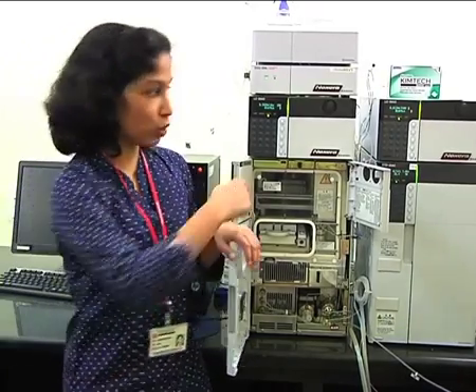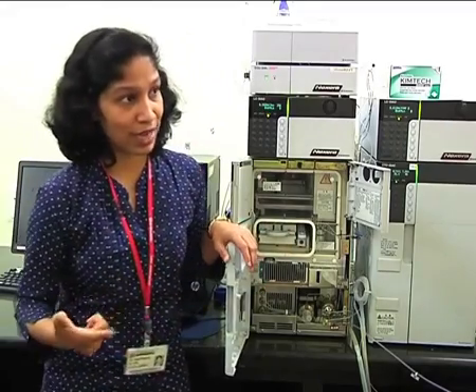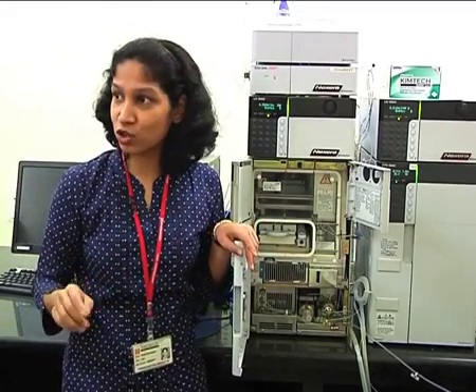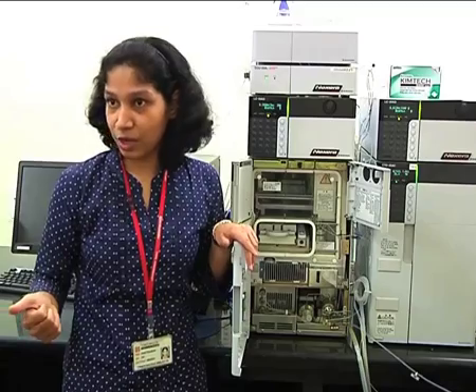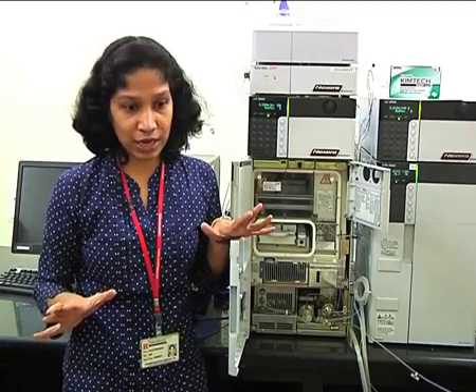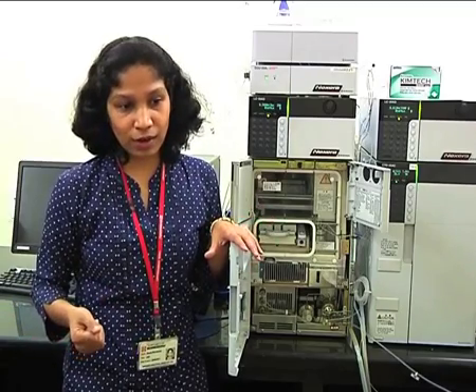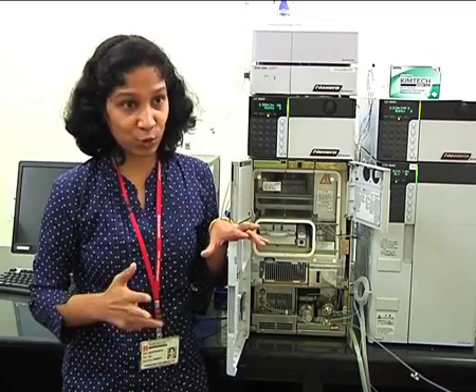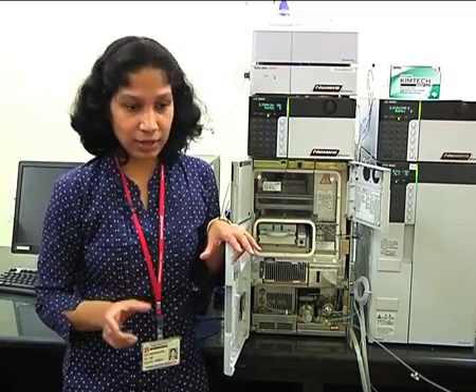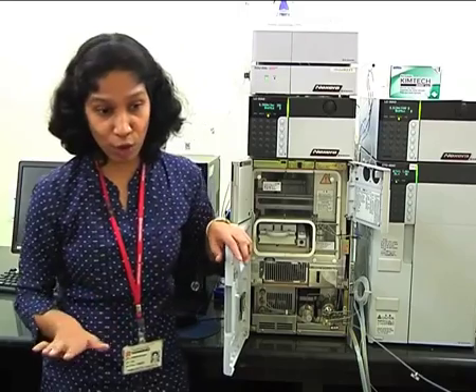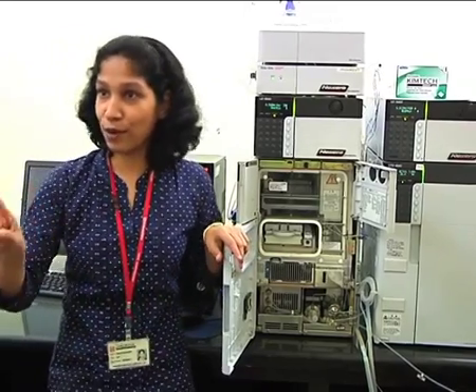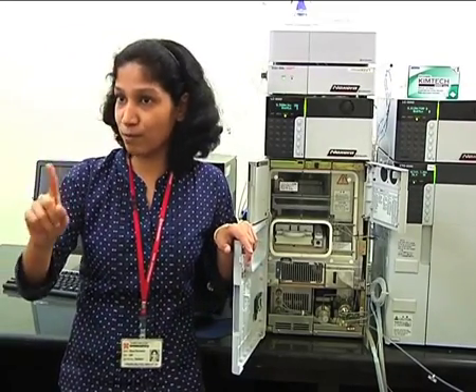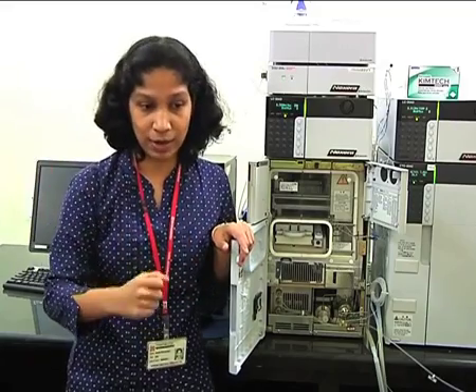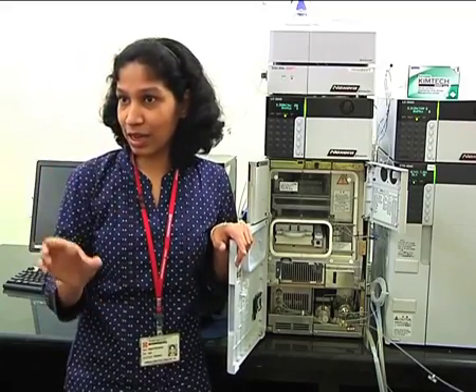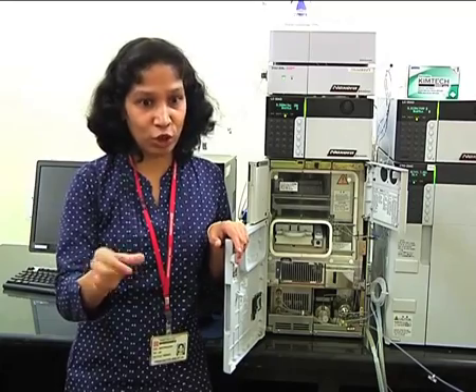Fine. Also, this is a fast autosampler. It takes only 10 seconds to inject 10 microliters of sample. So this particular function is very important when you perform fast HPLC kind of analysis. Because this is generally for small molecule assays, where you want to quantify only one particular compound in your sample, and your runtime is as short as 1 minute or 2 minutes.